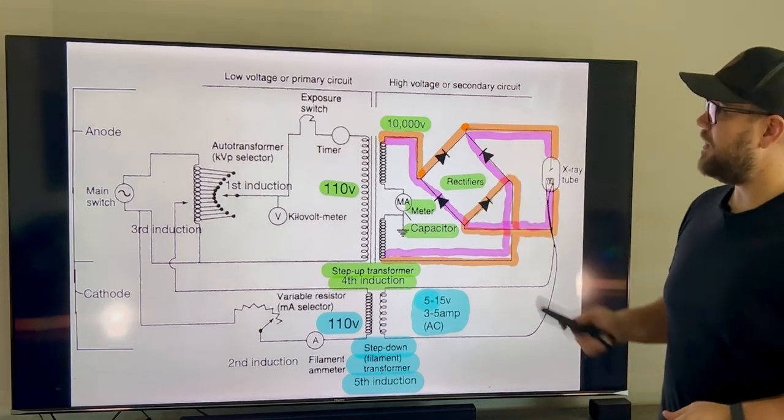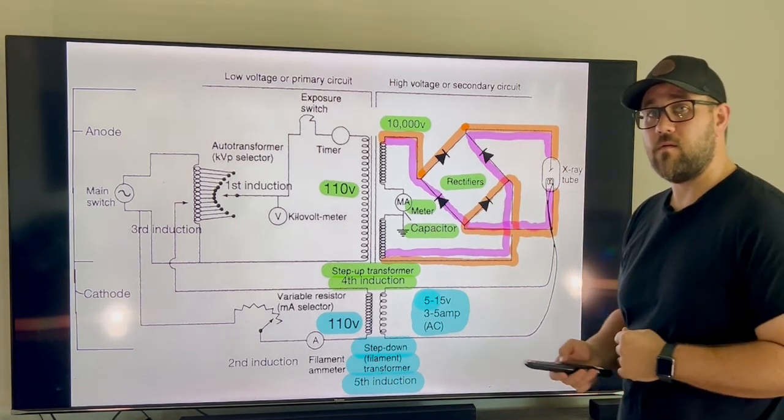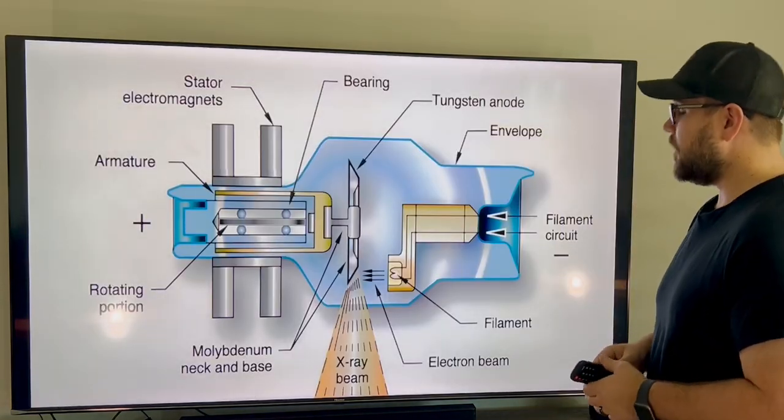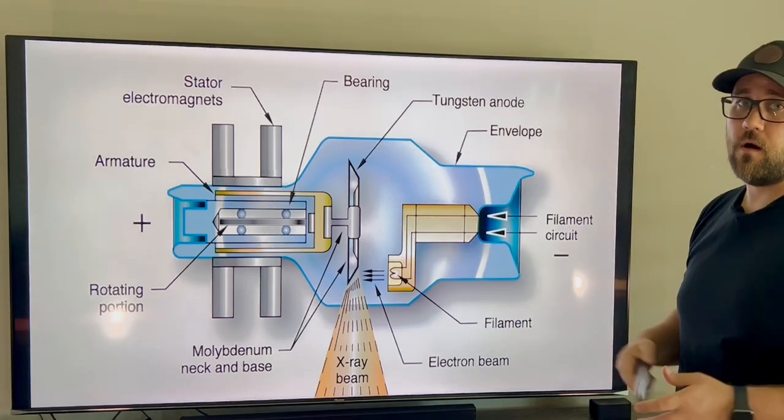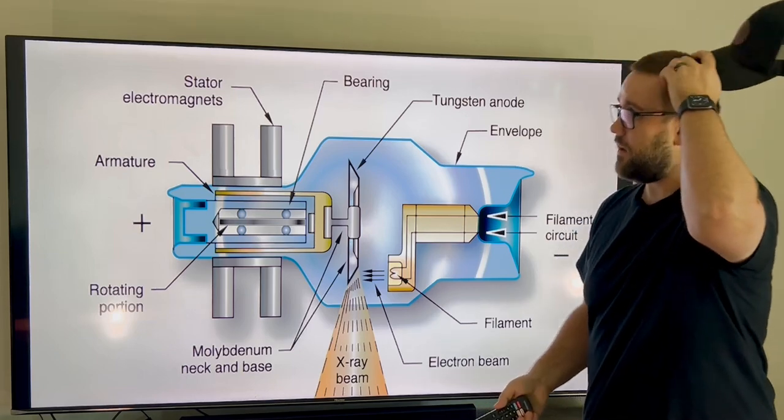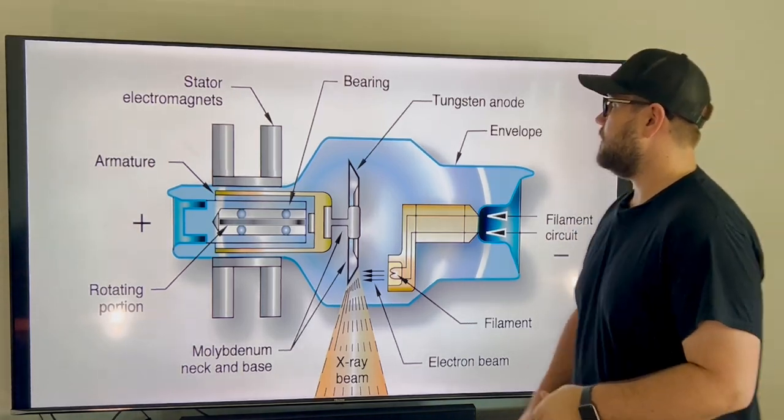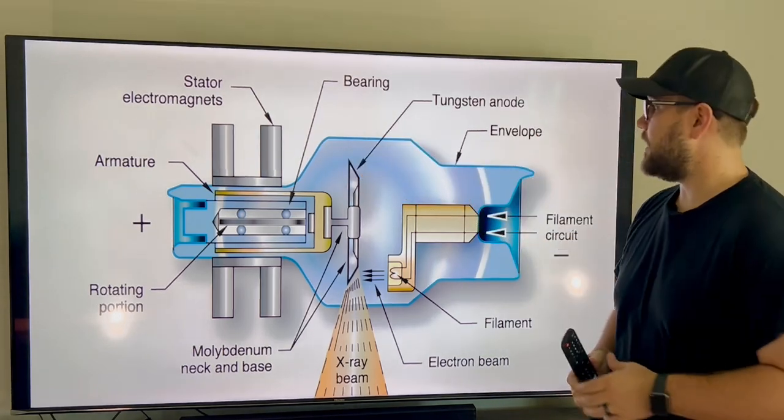So now that we've talked all about the circuit side, let's jump over to our envelope. Okay, so this is our envelope. Before we move too far on, I just want to talk about a few parts, kind of what they are. So on our anode side, we have our 10,000 volts pulsating DC coming in, and it's going to be electrifying our magnets, our stators. In turn, it'll rotate our armature or rotor. We have our bearings which are going to spin our tungsten anode.